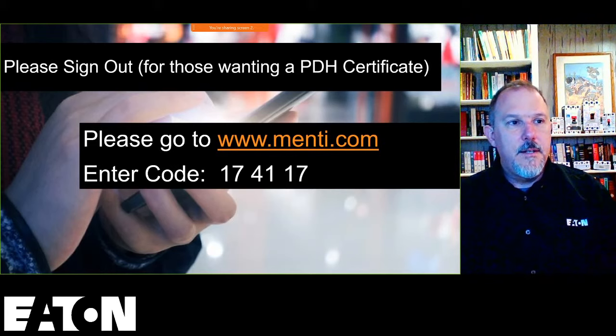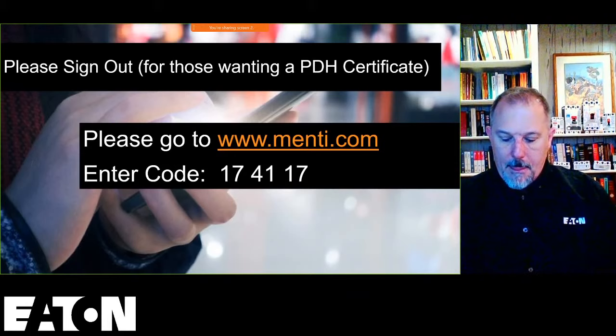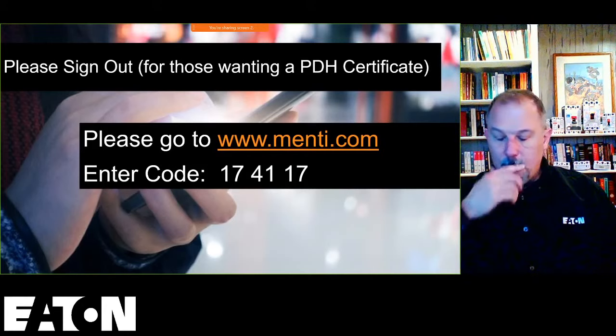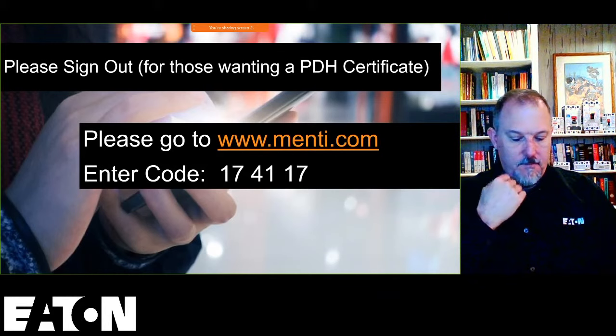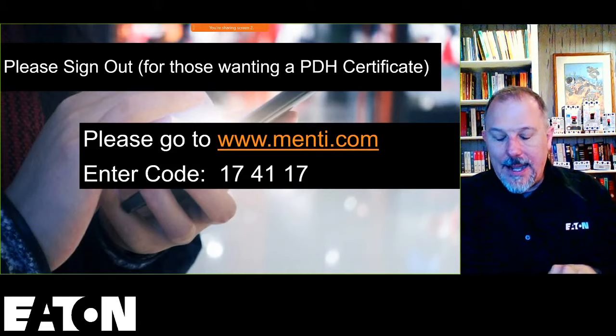Where does it tell you that the manufacturer has to make the calculations? I don't read that. It says it has to have. That's what 440.4(B) says. It has to have a nameplate. The nameplate has to tell you who built the product, what the voltage is, what the minimum circuit ampacity is, maximum ground fault short circuit, and other information. And then it tells the manufacturer how to derive those values using Article 440. So the electrician need only look at the nameplate because the mathematics are already done in accordance with the code.